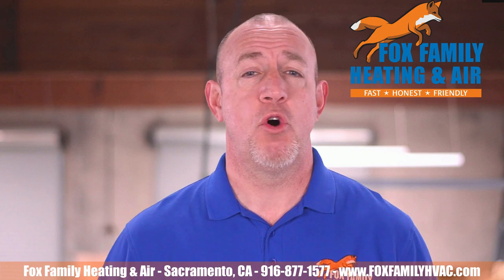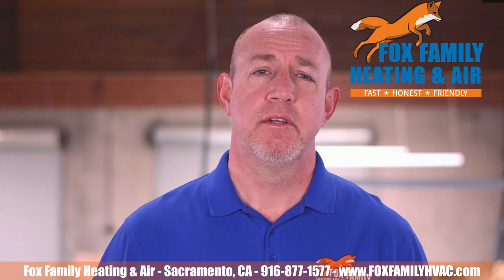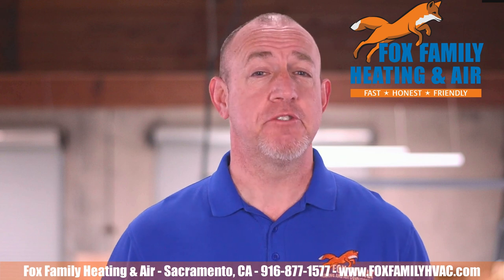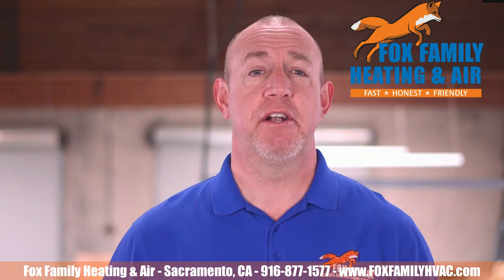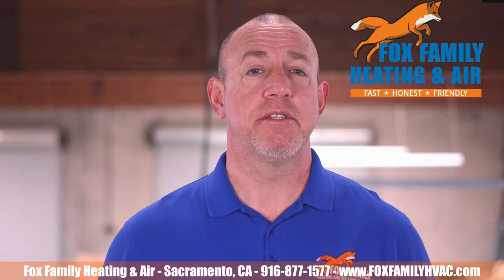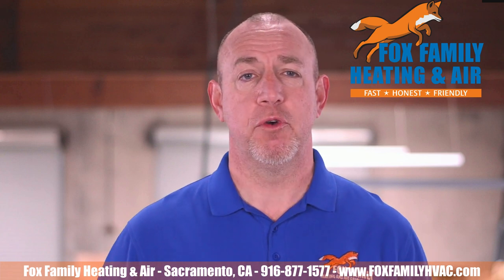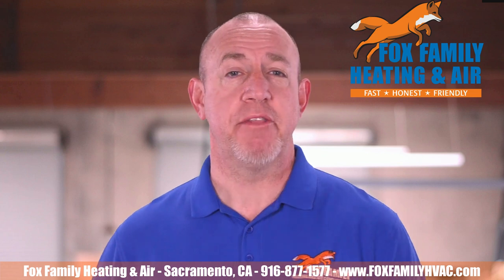The biggest issue that we hear from mobile home owners is airflow. Good, balanced airflow is a basic desire of an HVAC system owner. It's called central air conditioning, and the air delivery at every register should be sufficient for each individual room. The fundamentals of airflow are equal distribution at each register according to the size of the room. In a typical house, each room has a register and duct size specifically for that room — a 90-square-foot room might have a 6-inch duct with a 12-by-6 supply register, while a 45-square-foot bathroom might only need a 4-inch duct with an 8-by-4 supply register. Designing the ductwork this way will make sure that each room feels the same temperature.